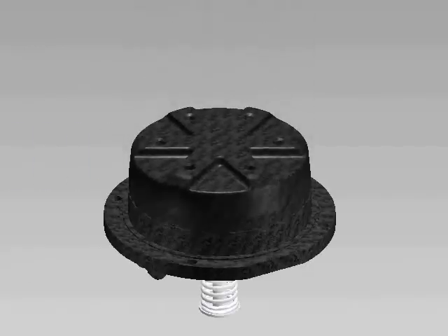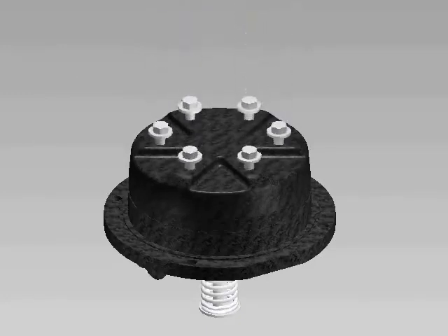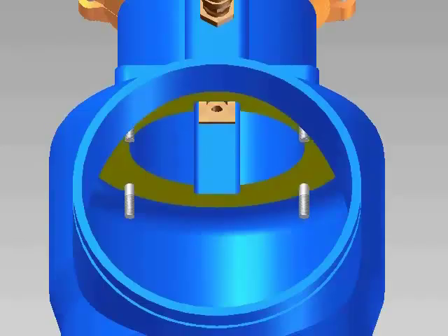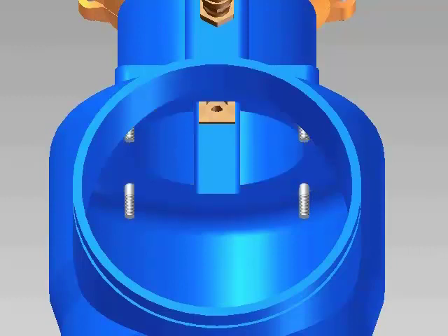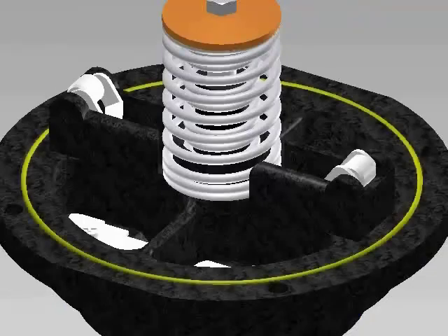Reassemble the check and tighten the retainer bolts evenly. Clean and inspect the O-ring sealing area in the body. Next you will lubricate the seat O-ring.